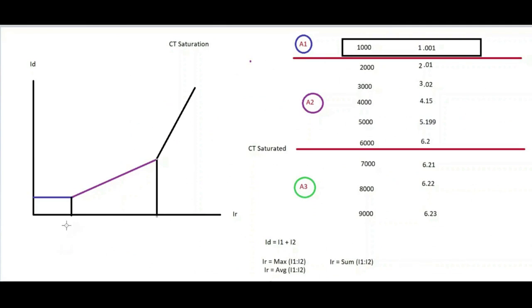This one, let's call it breakpoint 1. Normally this will be your full load current, because up to full load current, 1000 amps, you are in A1. Then your CT saturation current, this is called breakpoint 2. After BP2, you will be in the saturation region. So the electrical understanding which we had here, we have graphically transformed here.